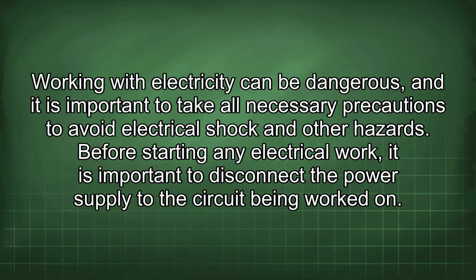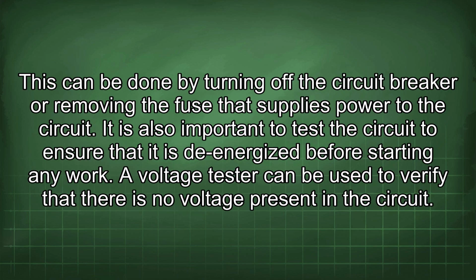Working with electricity can be dangerous, and it is important to take all necessary precautions to avoid electrical shock and other hazards. Before starting any electrical work, it is important to disconnect the power supply to the circuit being worked on. This can be done by turning off the circuit breaker or removing the fuse that supplies power to the circuit. It is also important to test the circuit to ensure that it is de-energized before starting any work. A voltage tester can be used to verify that there is no voltage present in the circuit.